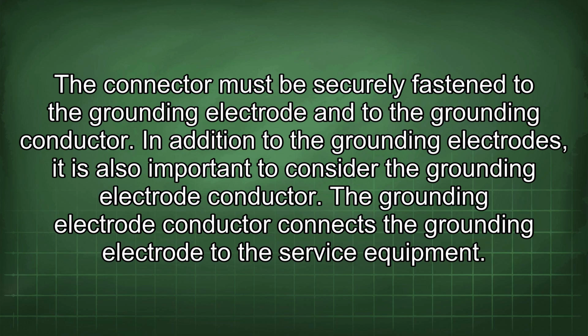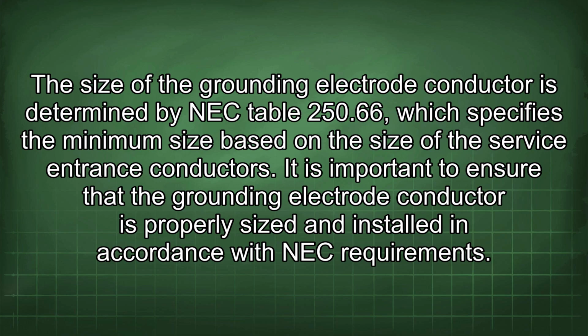In addition to the grounding electrodes, it is also important to consider the grounding electrode conductor. The grounding electrode conductor connects the grounding electrode to the service equipment. The size of the grounding electrode conductor is determined by NEC Table 250.66, which specifies the minimum size based on the size of the service entrance conductors. It is important to ensure that the grounding electrode conductor is properly sized and installed in accordance with NEC requirements.